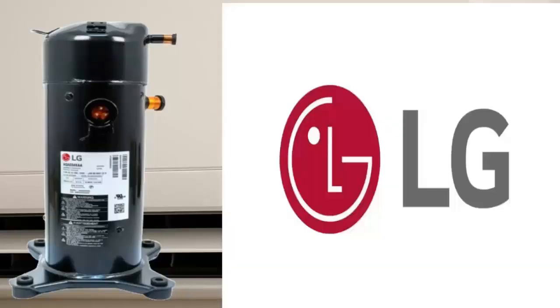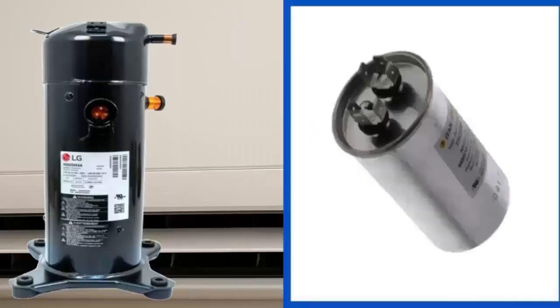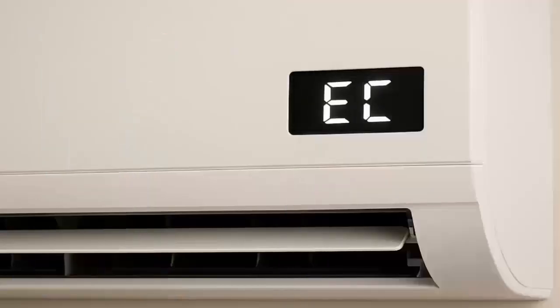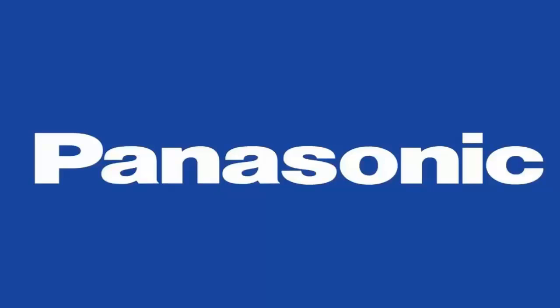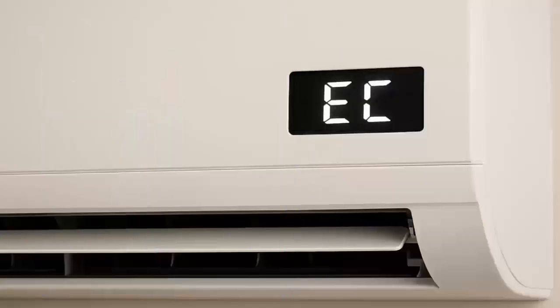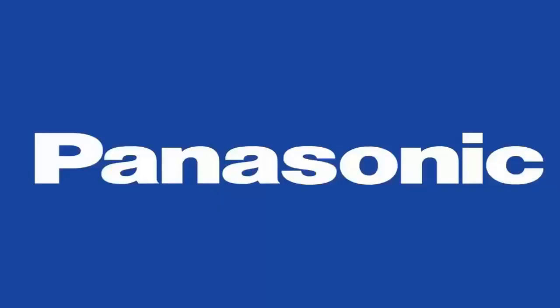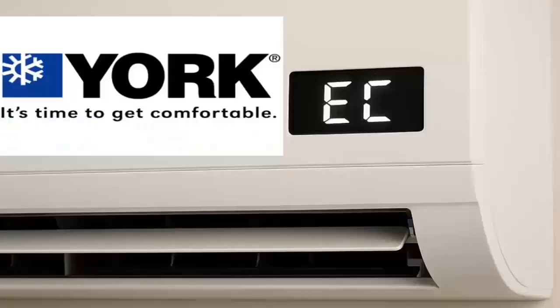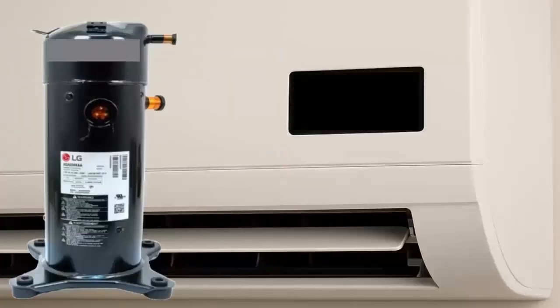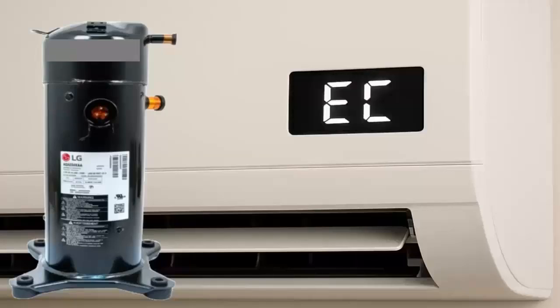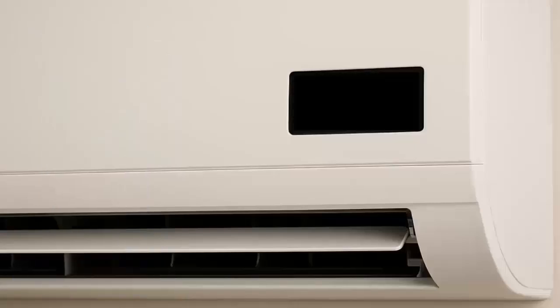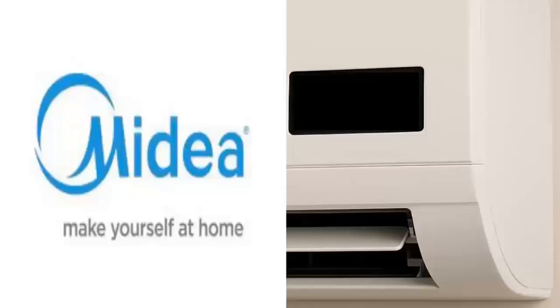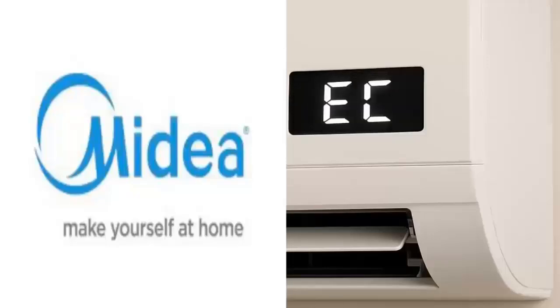This issue has been reported in: A. For LG, technicians suggest that a defective capacitor can prevent the compressor from starting. B. For Panasonic, code EC has also been seen due to a faulty outdoor fan capacitor. C. For York, especially in inverter models, code EC is associated with compressor problems. D. For Midea, in some models, EC is triggered by outdoor fan capacitor failure.